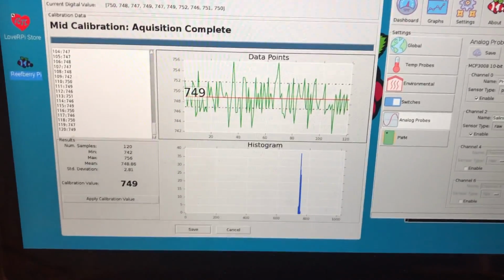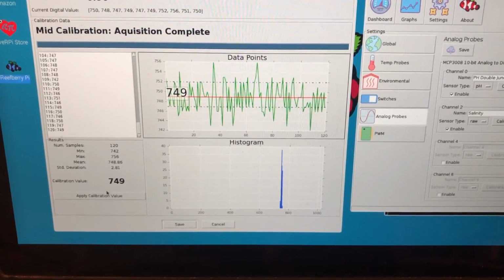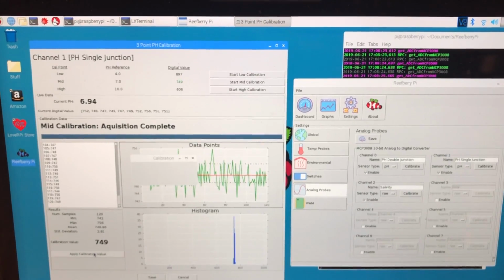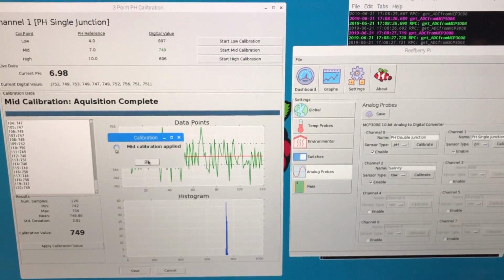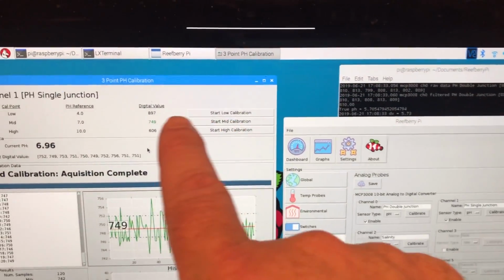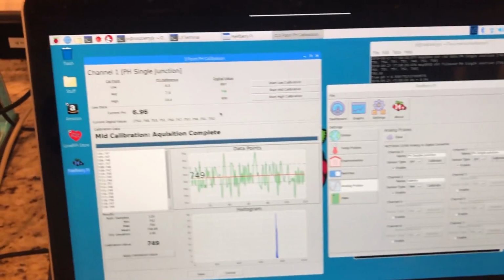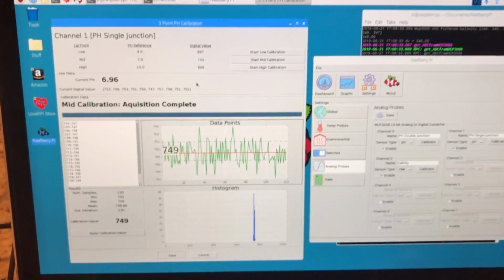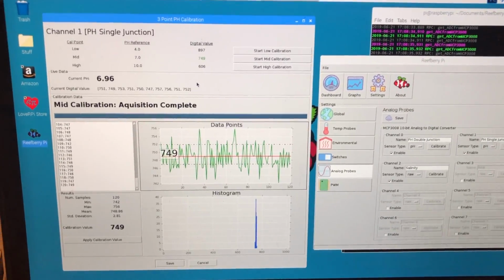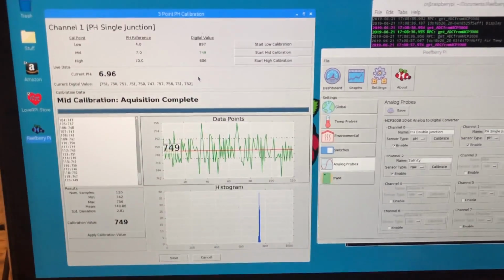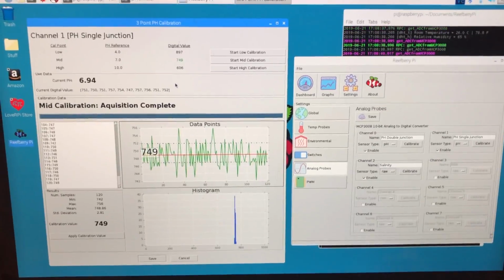If I was happy with that number, I will say apply the calibration value. It says, okay, the mid calibration was applied. I see that's now green, which means yes, I just calibrated it at that point. I'm going to go ahead and do the same thing for the low and the high, and then we should have a fully calibrated probe. So I'll be back in just a minute.